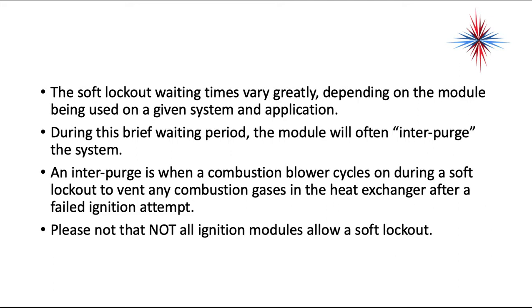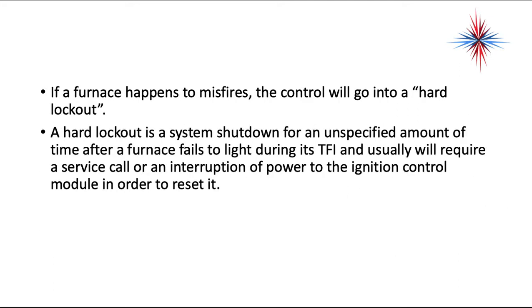Please note that not all ignition modules allow a soft lockout. If a furnace happens to misfire, the control will go into a hard lockout. A hard lockout is a system shutdown for an unspecified amount of time after a furnace fails to light during its trial for ignition, and it will usually require a service call or an interruption of power to the ignition control module in order to reset it.